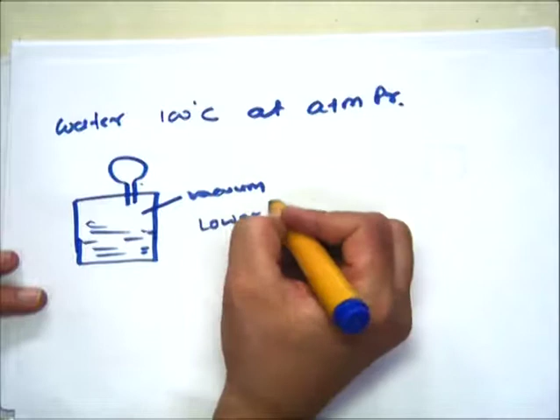Then there's the steam jet refrigeration system. The concept used is that water generally boils at 100 degrees centigrade at atmospheric pressure. But if I have a closed container filled with water, and I maintain a vacuum on the surface, meaning pressure below atmospheric, I can make the water boil at 5 degrees centigrade.